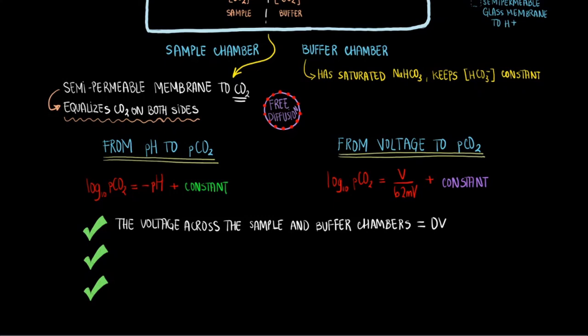Second, while the Ag-AgCl electrode would get consumed over time in a Clark electrode, which measures the partial pressure of oxygen, the silver-silver chloride electrode does not get consumed over time in the Severinghaus PCO2 electrode.